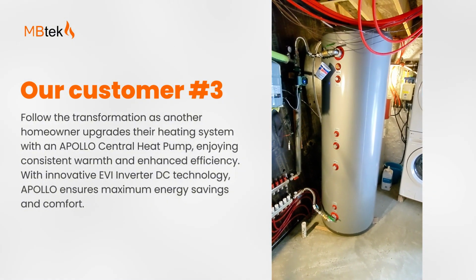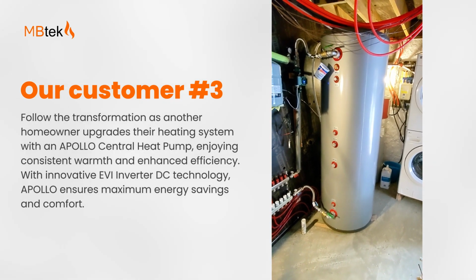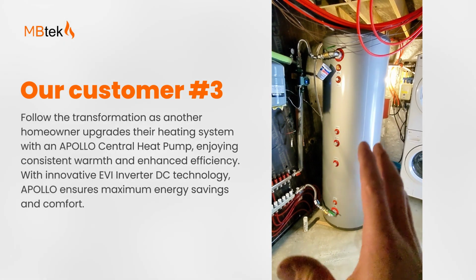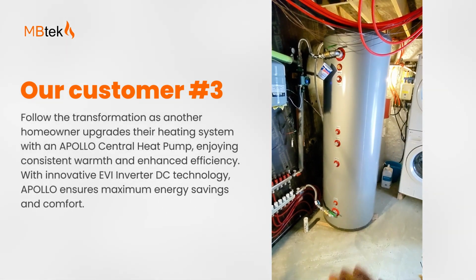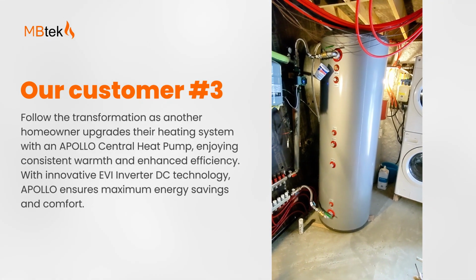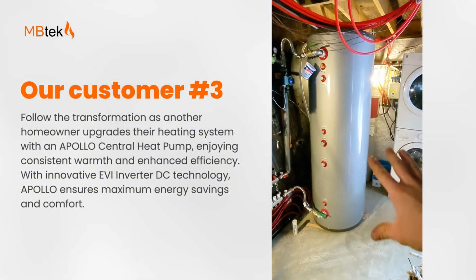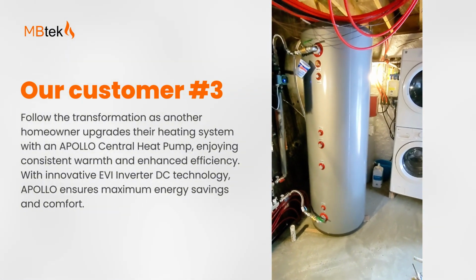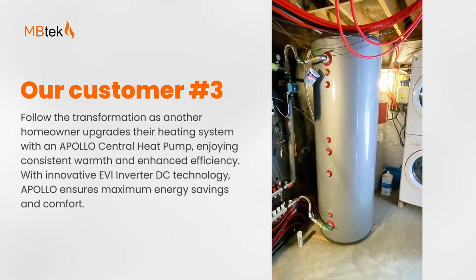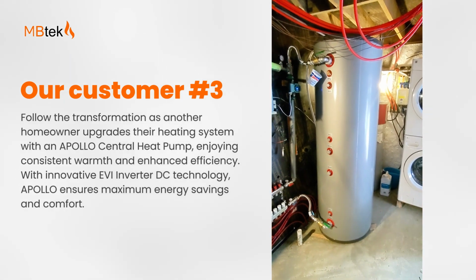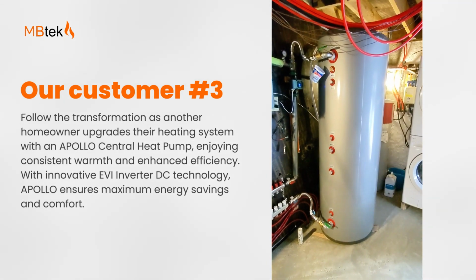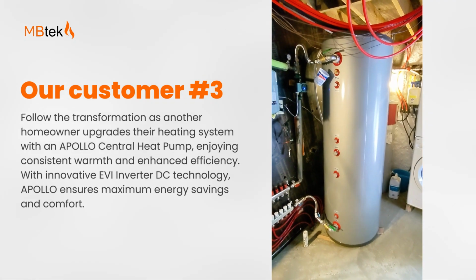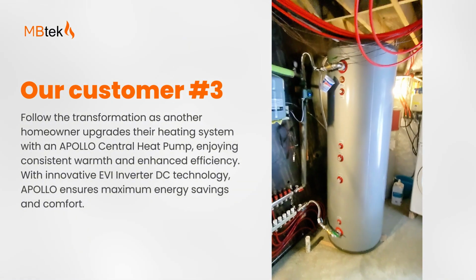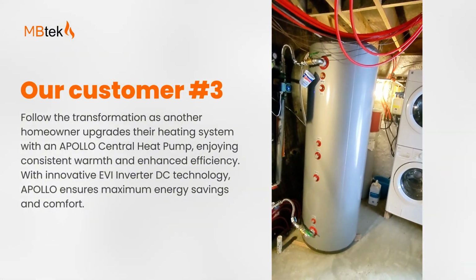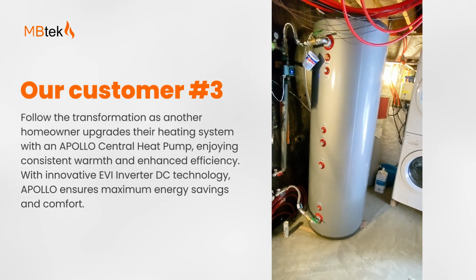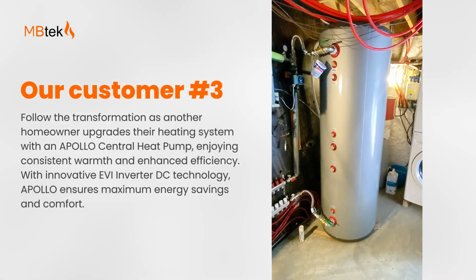So I'm saving a lot of money by just running the parts of the system on glycol and water that are actually in danger of freezing, which is only all the outside parts, the heat pump and the lines that go out to the heat pump. So that has to be freeze protected. Obviously, if there's a power outage and no water is being circulated through the heat pump unit outside, water would just be sitting there. The pipes would freeze and burst and break all kinds of stuff. So that has to be freeze protected.